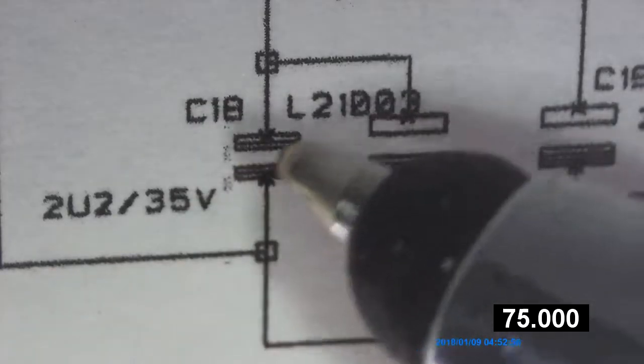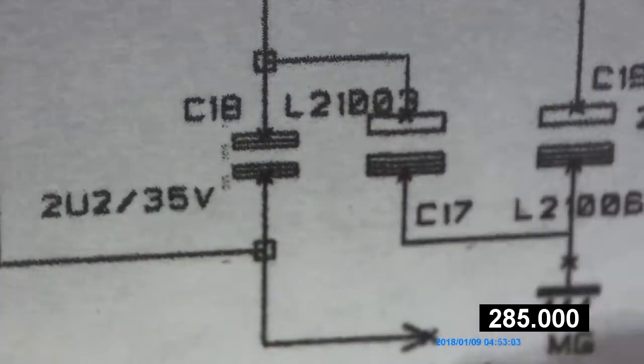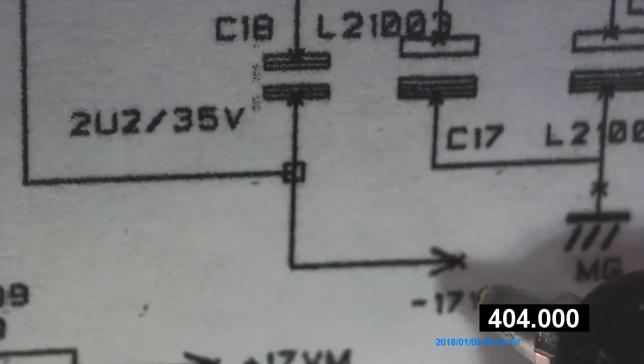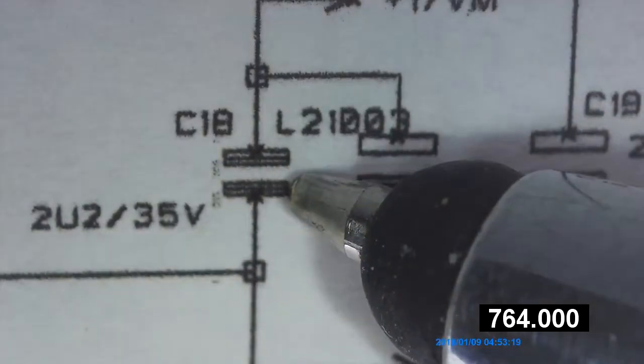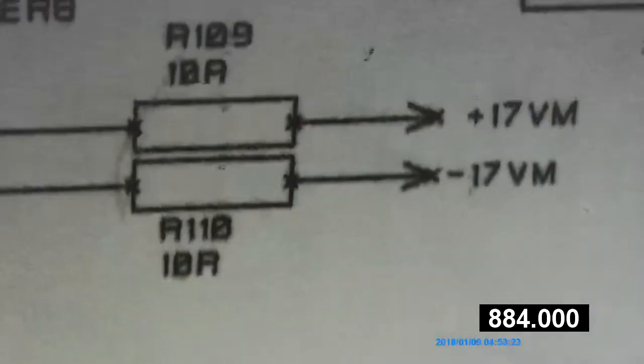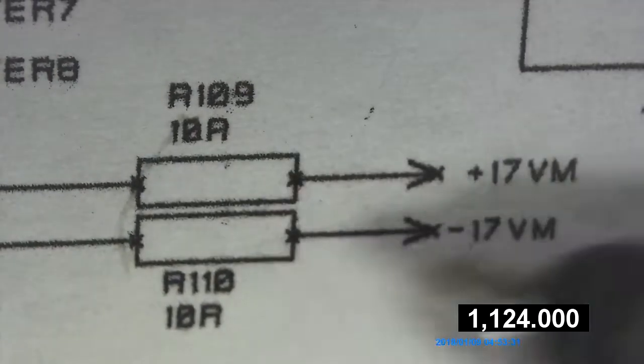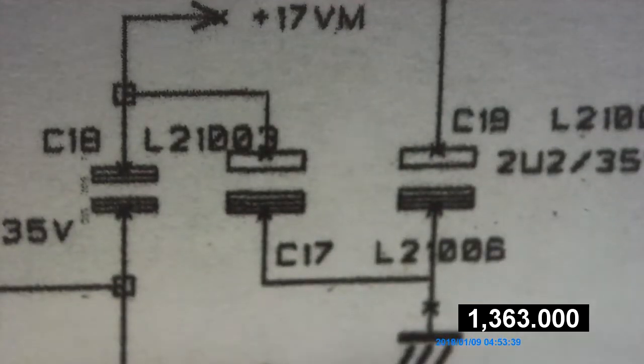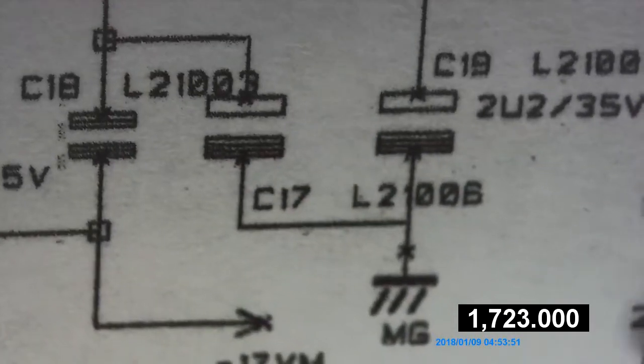This is the capacitor that shorted out — it's next to C19. The ground is the negative 17 volts; it shorted out from the positive, causing resistor R109 to literally burn up. R109 is down here — that's the one that cooked, causing the card to go out. I thought it was an IC dual op-amp, but it turned out it wasn't. Once I replaced this capacitor and put it in the board, it actually worked. It's a 2.2 microfarad, 35 volt AVX capacitor — C18.